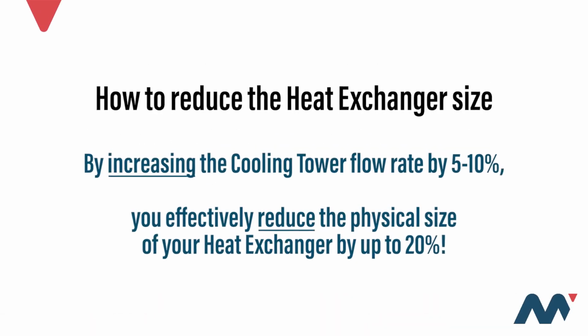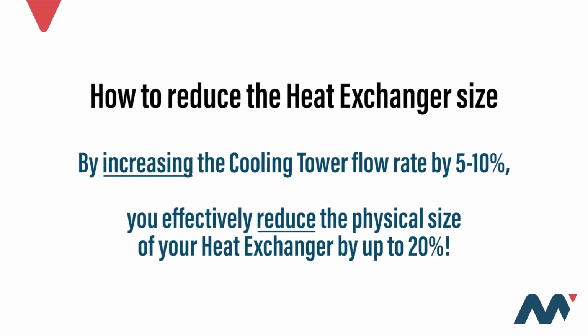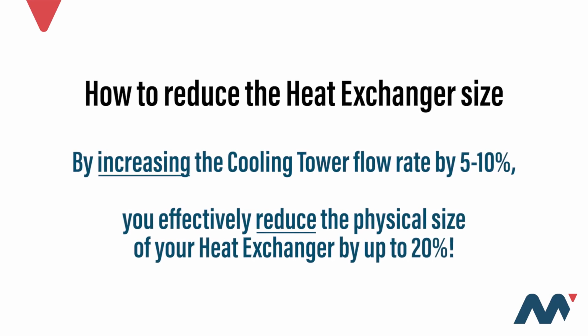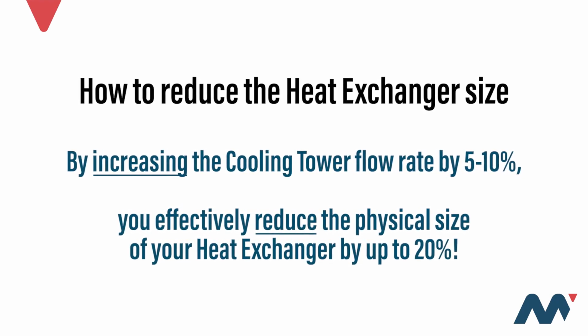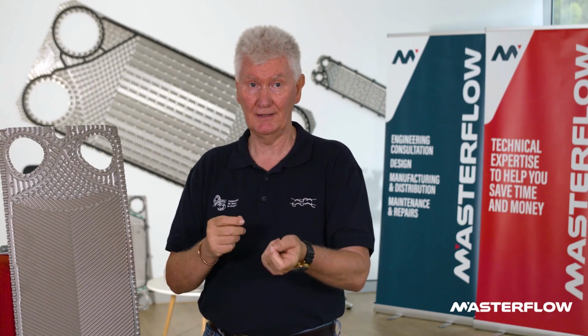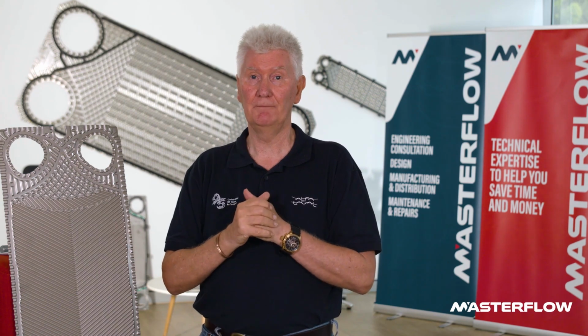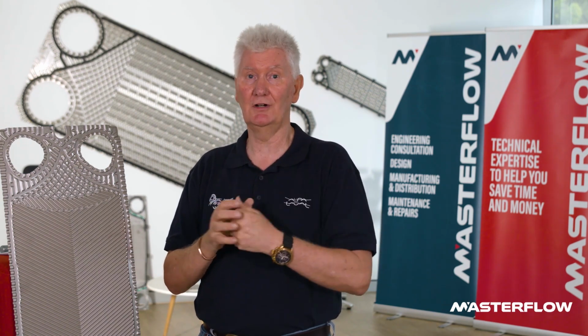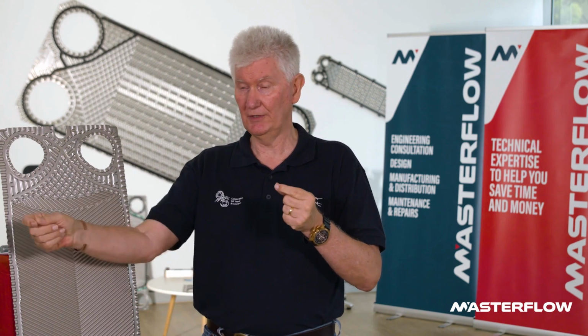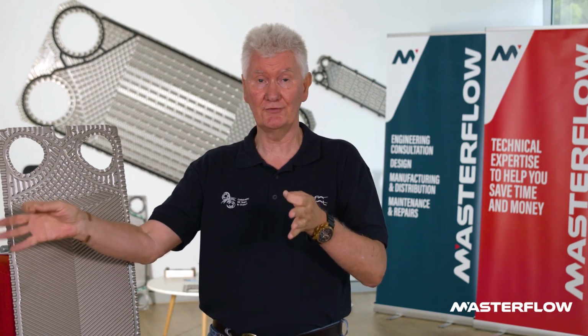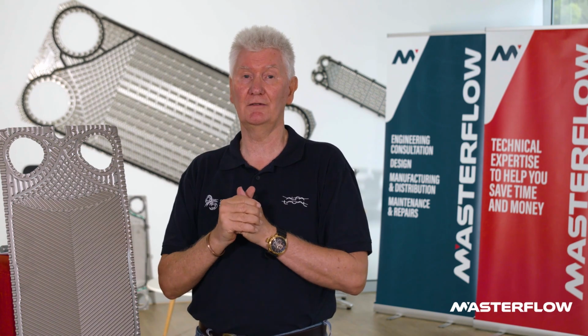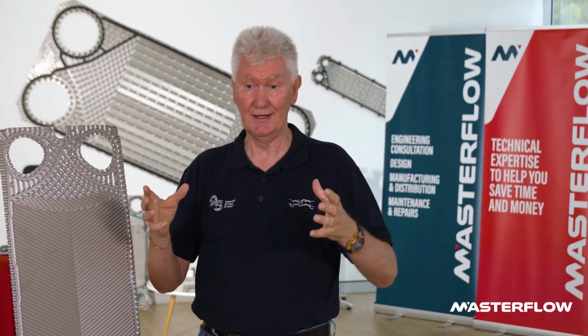If we were allowed to add, say, a 5 or 10% increase to the cooling tower flow rate, the size of the heat exchanger could actually drop by about 20%. In one of my AHRI presentations, I show consultants how that is manifested. If they look at that as a summertime option, normally the heat exchanger can get smaller for its average running, and they just increase the tower flow rate by 5 or 10% while maintaining the required heat load from the same heat exchanger.